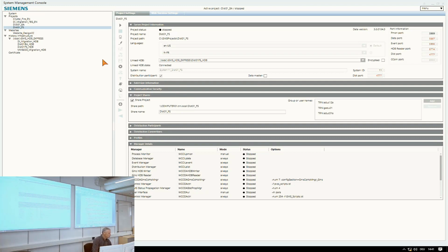While I am on this project, it is important that you know that we have to share the projects, just like we have to do when we have a remote client or a FEP with an installed client where we need to access the project on the project server. We have to share the project with all the operating system users, if you will, that are going to be logging into that Desigo CC project.